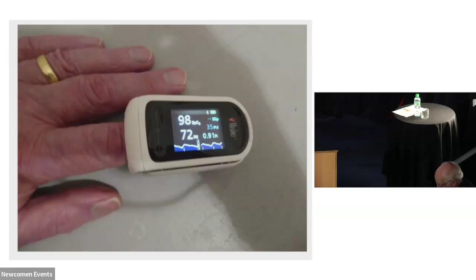So we then come to the dangerous ones. They look as though they're working and they're not, and they're the ones you've really got to be switched on about. Accuracy: the cheap ones can be very inaccurate, whereas the expensive ones are within 1% of the read. It's what they're calibrated to do. They are all calibrated for human adult hemoglobin A, and any other abnormal hemoglobin. If you don't know it's there, you shouldn't trust the pulse oximeter.